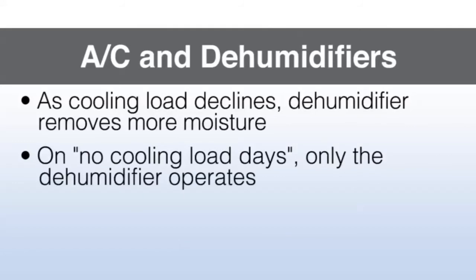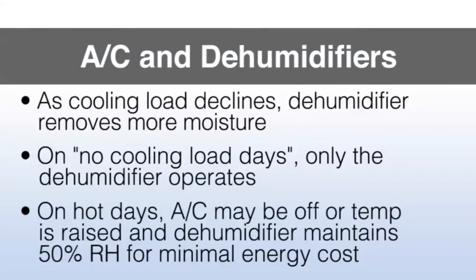AC and dehumidifier interaction is important at this stage. As the cooling load declines, the dehumidifier removes more and more moisture. On no-cooling-load days, the dehumidifier only operates. On hot days when the home is unoccupied, the AC may be turned off or the temperature raised. The dehumidifier maintains 50% relative humidity for minimal energy consumption, regardless of what the temperature in the home is. Thank you.